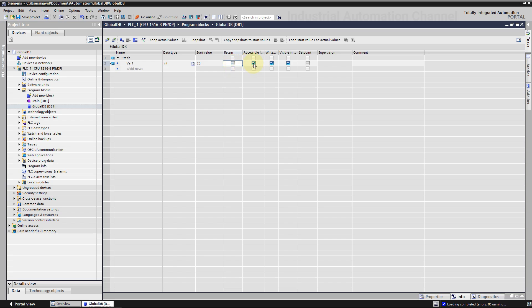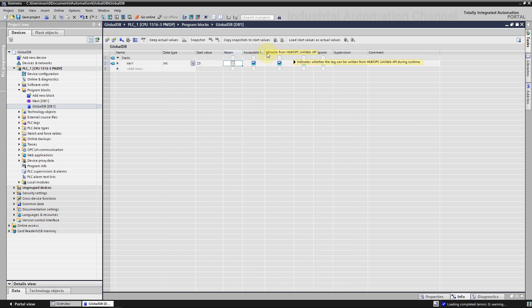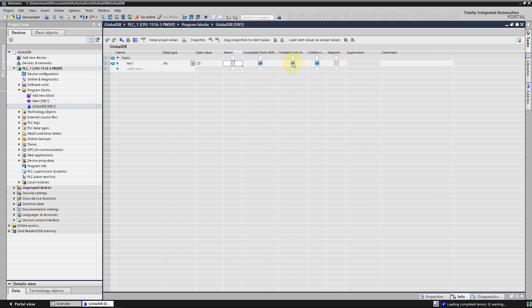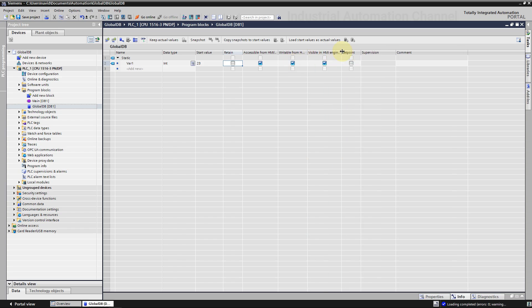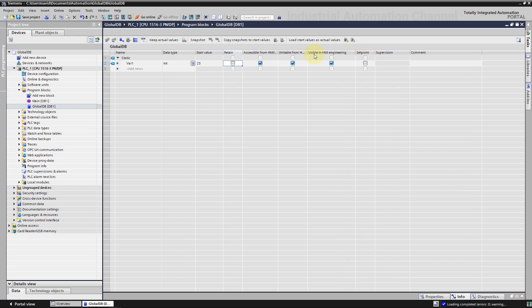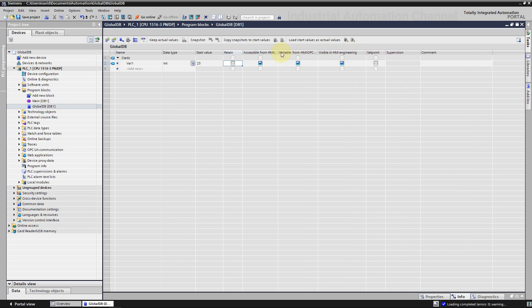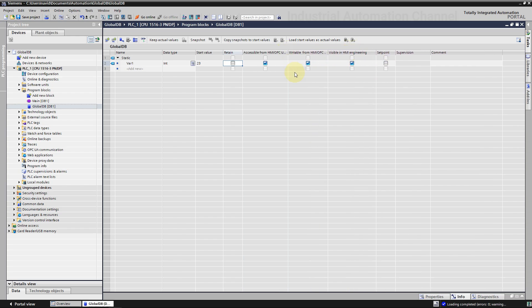In a global DB you can define if a variable can be visible from the HMI tag tables or not. You can also define if this variable can be read or written from the HMI. The default setting for any declared variable in a global DB is that it can be accessed, read and writable from HMI. If you want to disable this feature for a variable, you can uncheck the accessibility option for that variable.